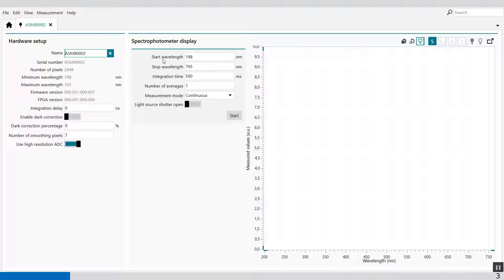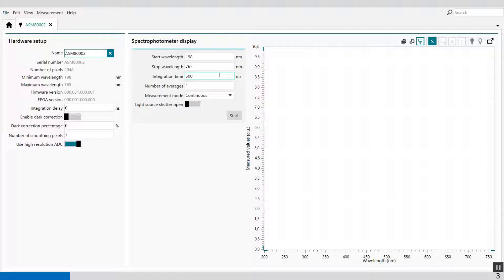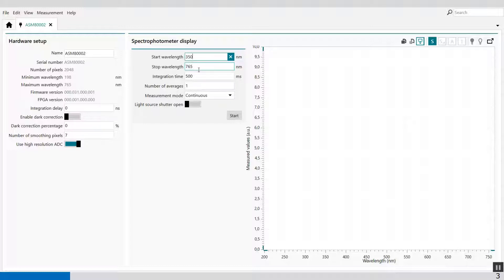Then we have the spectrophotometer display. Here we have the start wavelength, the stop wavelength, integration time, number of averages, and the measurement mode. The start wavelength is an input field which can be used to specify the start wavelength in nanometers; it is automatically set to the lowest possible value supported by the spectrophotometer — in this case 198 nanometers. I modify this to 350 nanometers, and my stop wavelength I decrease to 500 nanometers.